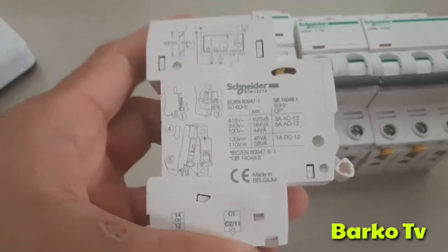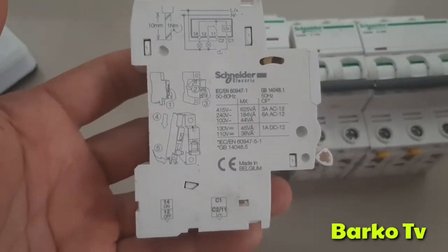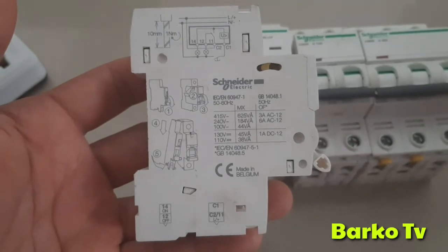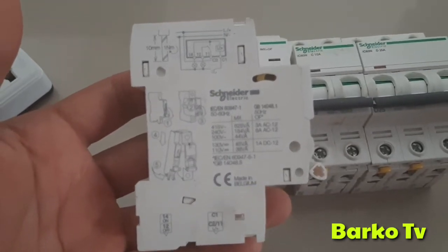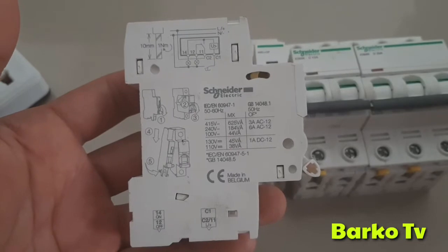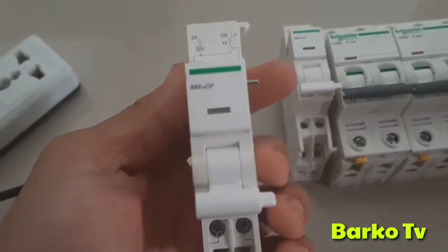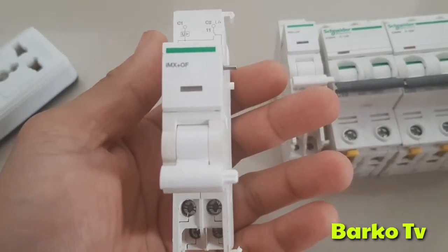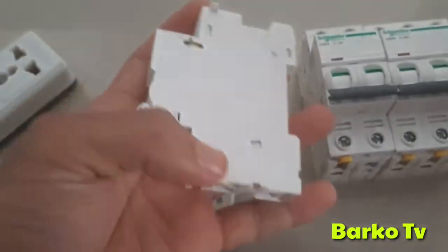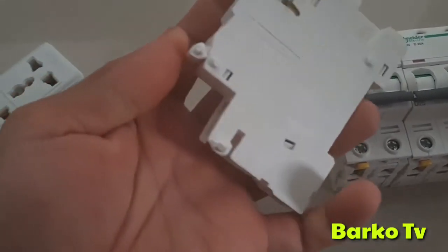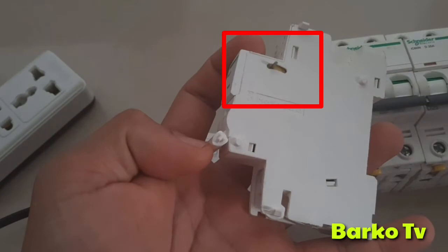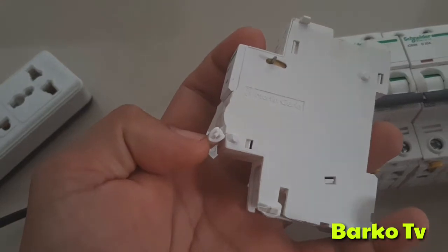This is the attachment for the MCB, miniature circuit breaker, brand Schneider. This device activates at 100 volts AC to 415 volts AC. When you supply it, it will trip within that range. Also, 110 volts DC to 130 volts DC can also activate. This device is good because it caters to AC or DC. This lever attached to the MCB so that if this activates, it will trip the MCB. This is the mechanism that connects the MCB.